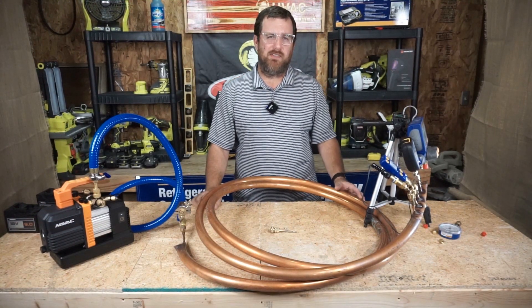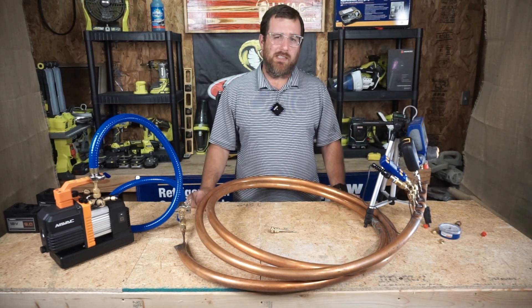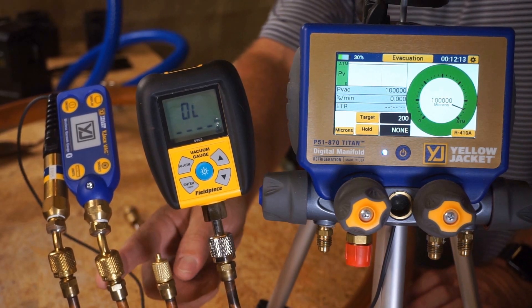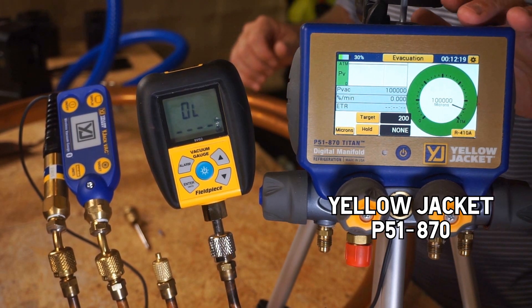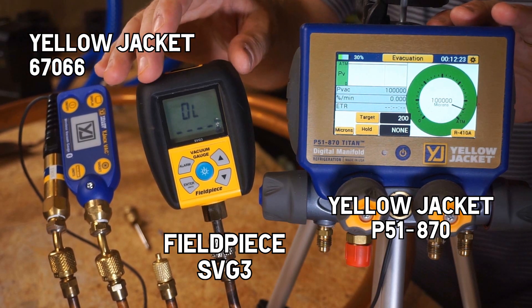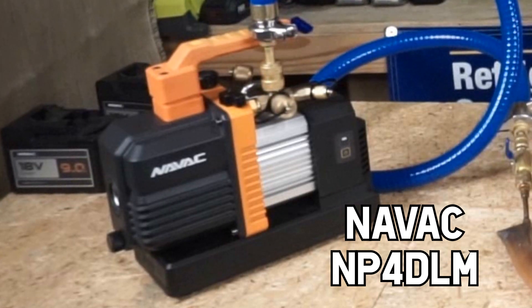My name is Zach Scioto from the HVAC Shop Talk podcast, and I'm here with my 40-ish foot roll of inch-and-one-eighth copper. I have made four taps, only using three today. I put three micron gauges on it: P51-870s, the new yellow jacket micron gauge, and a Fieldpiece micron gauge. I've hooked the other end up to the NAVAC 4 CFM vacuum pump.